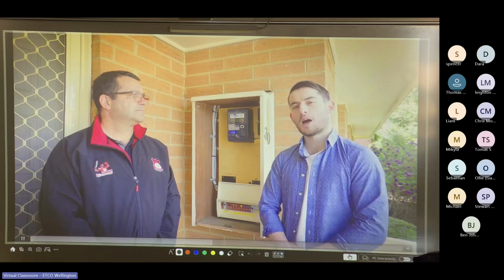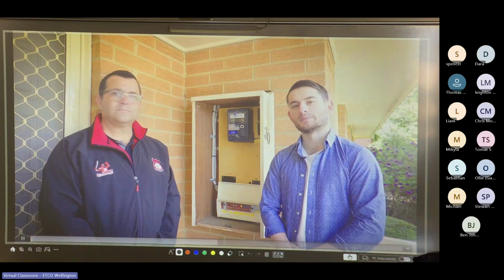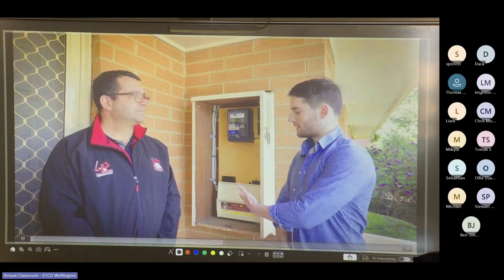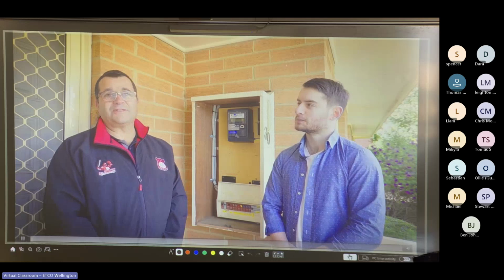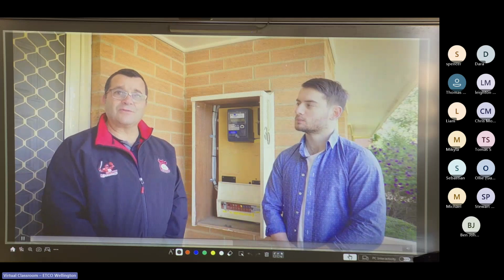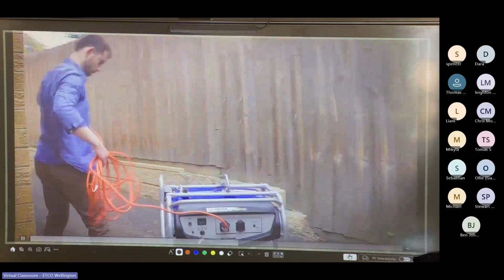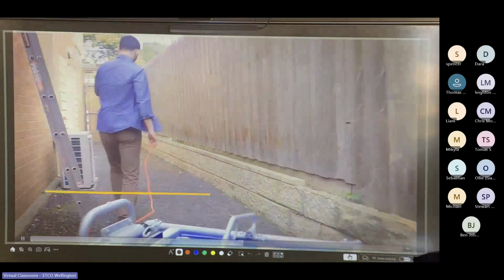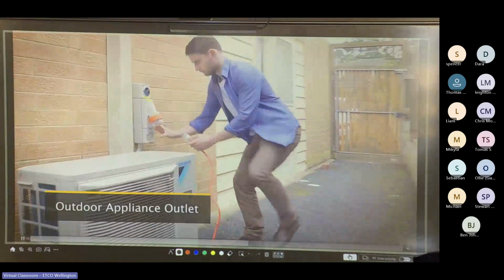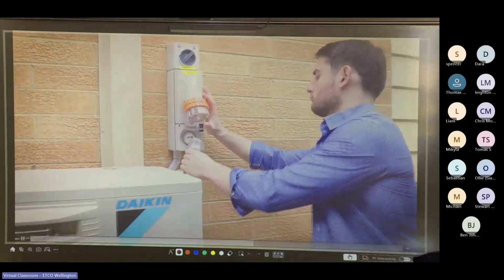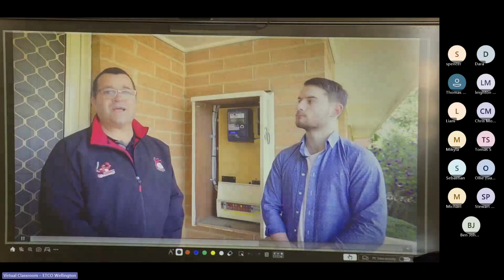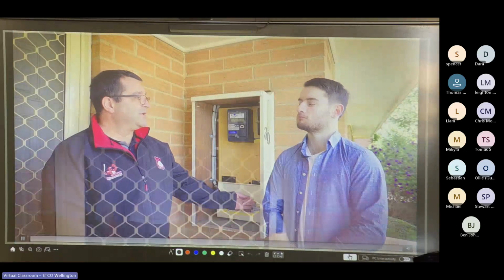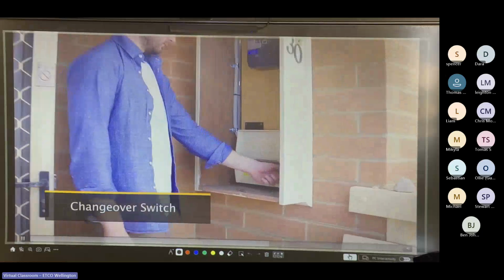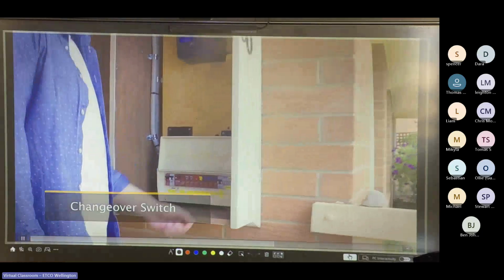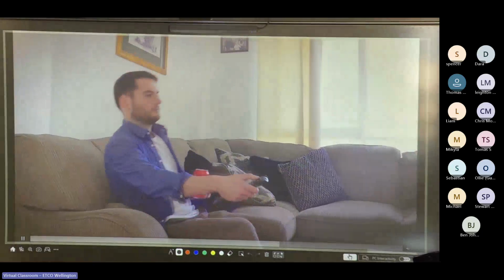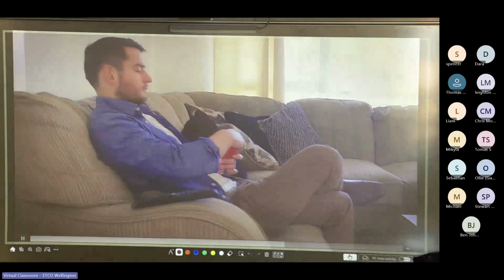Now, Silvano here is the Sparky who hooked up this home in Whittlesea. Tell us, Silvano, how easy is it to set one of these up? It's very simple to install a manual transfer switch. In your switchboard, you just need to install an appliance outlet outside the building. When you lose power, your generator will be plugged into your appliance outlet. You'll come back to your switchboard, change your switch from mains to generator. You are on generator power, and you plug in whatever appliance you need to power your house up.